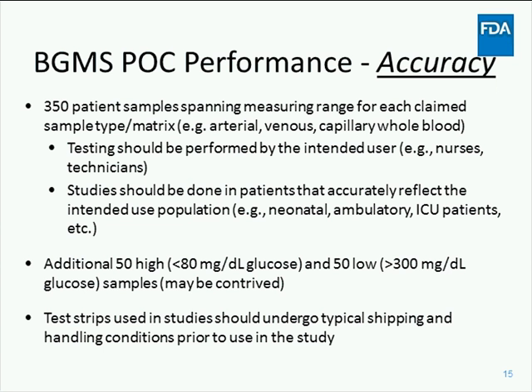The study should represent the actual claims made for the device and should include subjects that accurately represent the intended use population. A minimum of 350 patient samples per claim sample type or matrix should be used. Now, this is an increase from what we currently see. But this means that for each claim, such as an arterial, venous, or capillary blood claim, 350 samples for each type should be submitted. So these different sample types can be acquired from the same patient and be used for these different studies.